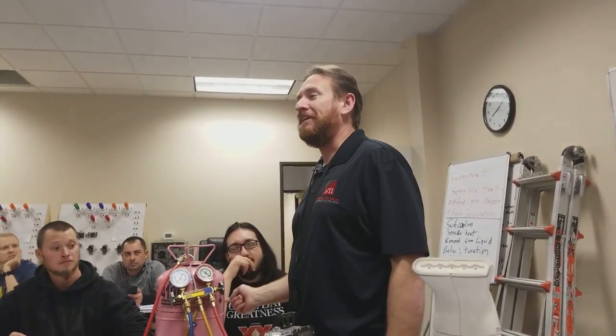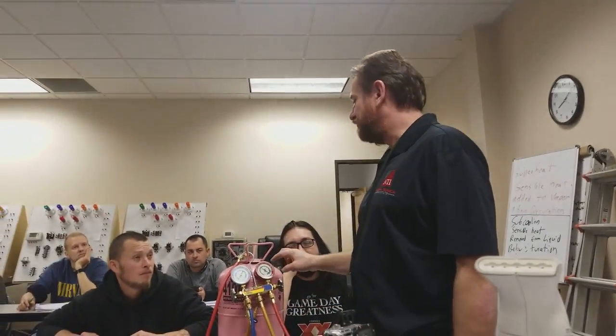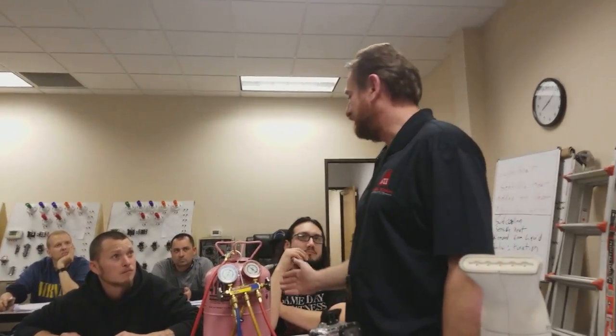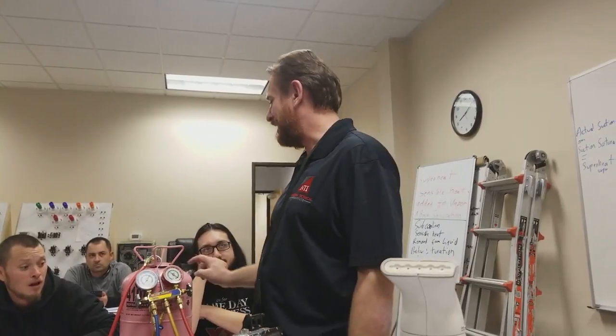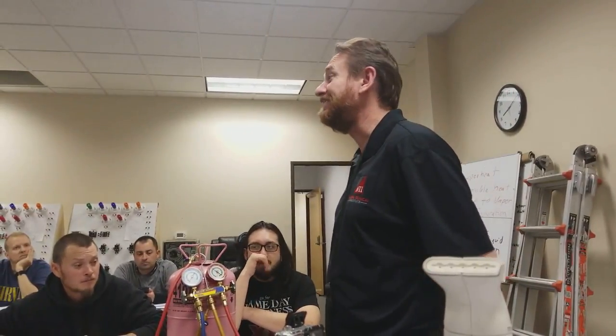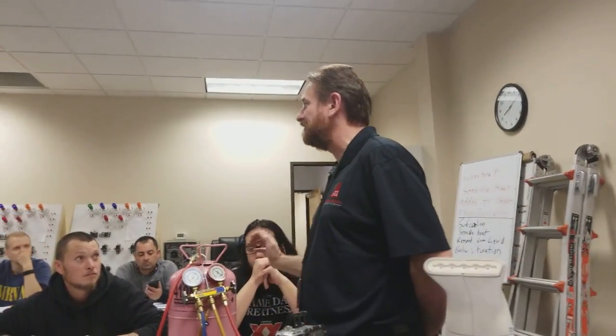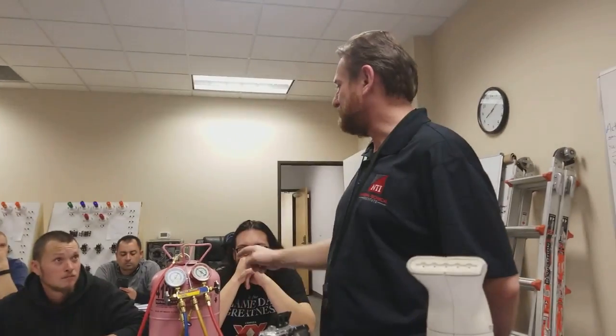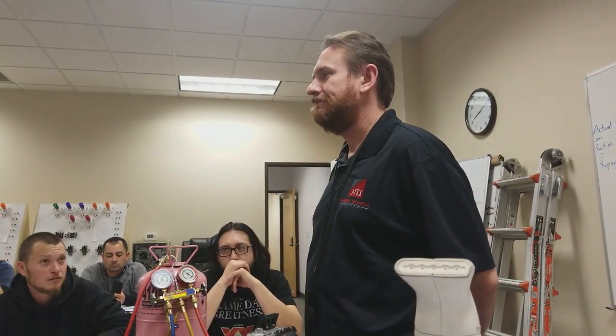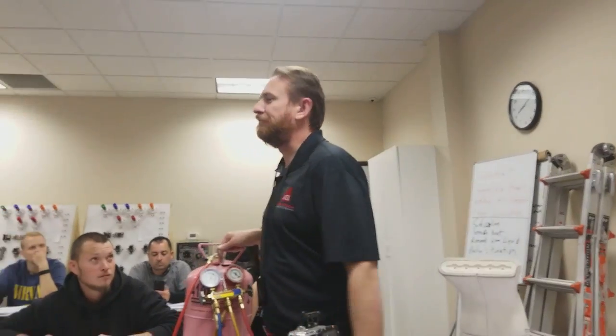It's at saturated, liquid and vapor together. I took my pressure and converted it to temperature. Does the temperature of the tank not match the temperature-pressure chart? Because it is, without a doubt, saturated. It's not actively changing state, but there is liquid and vapor together, right? What happens if I drop the temperature of that tank? It's going to drop the pressure, it's going to drop the saturation. I'm going to put this in the freezer. We'll revisit this a little bit.